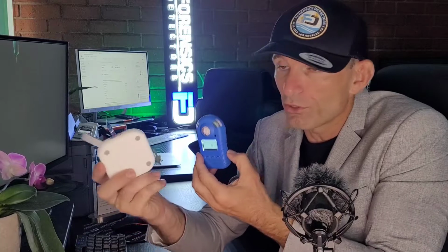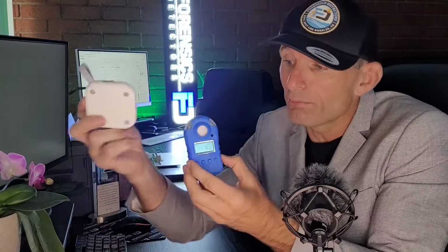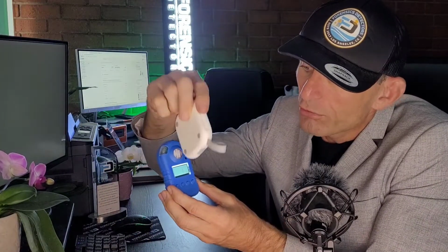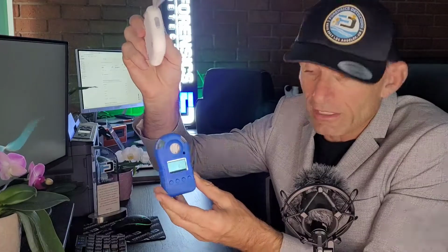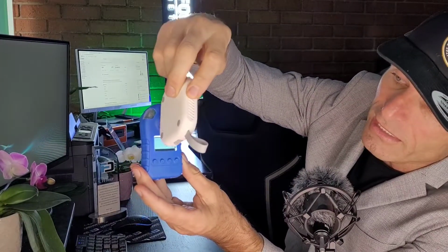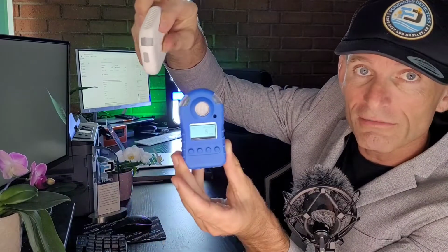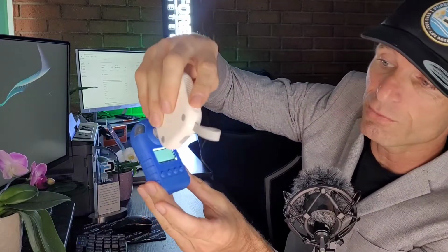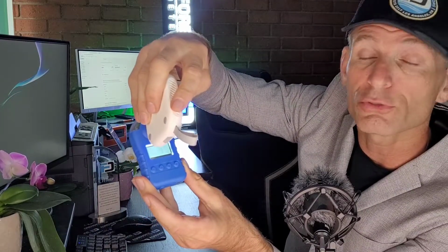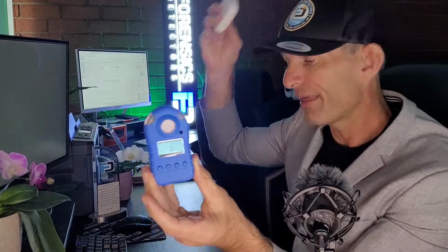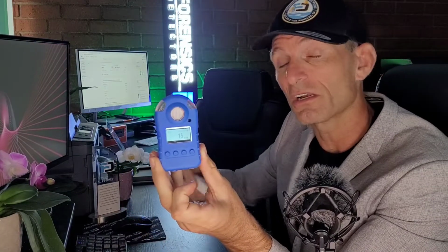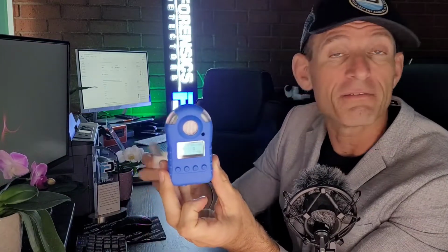So what you have to do when you're using this ozone generator to do a little bump test, you have to put it sort of close by and then flick it back, okay, folks? You don't wanna keep holding it there and then you're gonna blow out the sensor, okay? You just wanna give it a little tap and you wanna see it bump. That's what a bump test is. You just wanna bump it enough where the alarms are triggered, okay? Bang. That was right there, a bump test. I didn't exceed 100 ppm and I gave it a little bump.